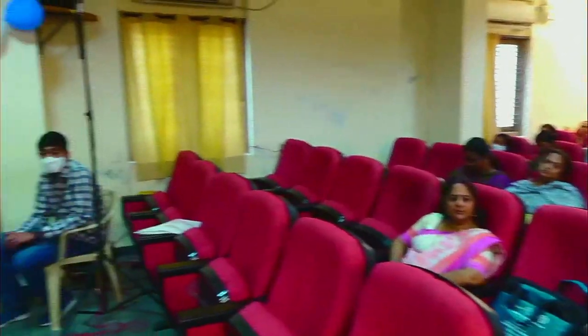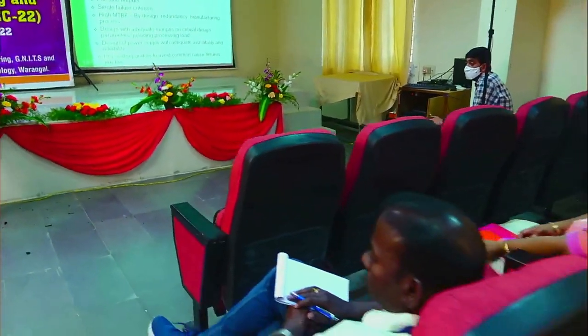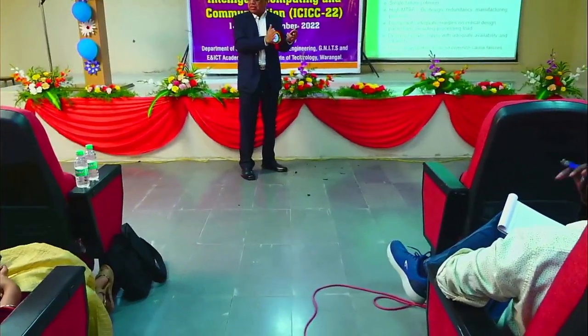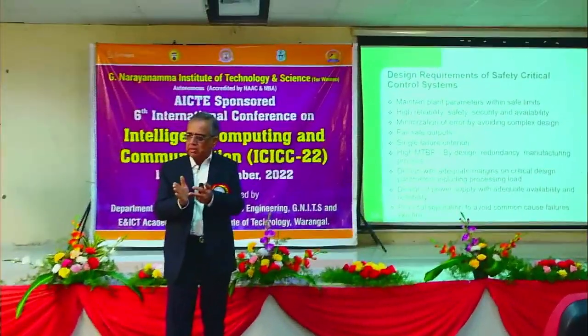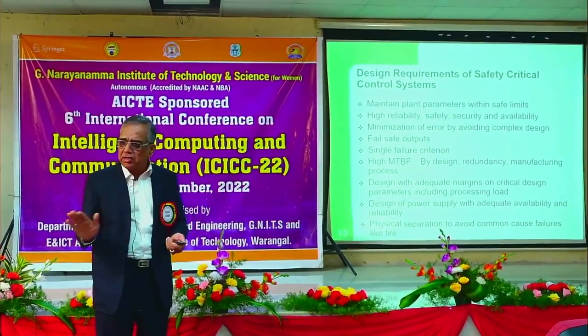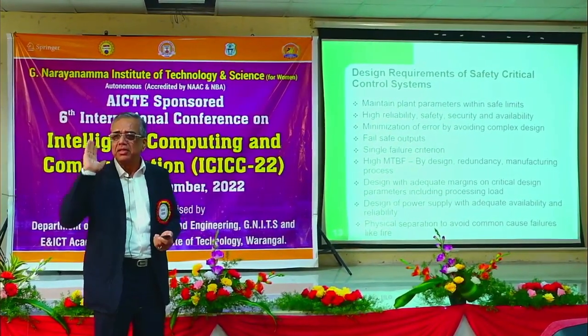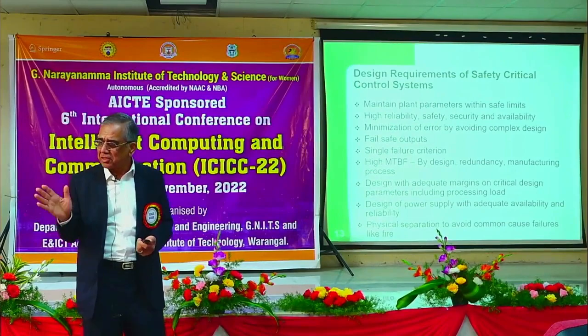So I told you there are 2 power supplies. Again, in a triplicated system, each will have 2 power supplies, and there will be 3 UPS, not a single UPS, which will be connected to these power supplies. So suppose there are 1, 2, 3 UPS, and I have got 3 systems A, B, C. One will get connected to A and B, 2 will be connected to B and C, the third will be connected to C and A, and those will be connected to the different main and standby power supplies. So unless all the 3 UPS fail, or unless all the power supplies fail, your power control system is available.